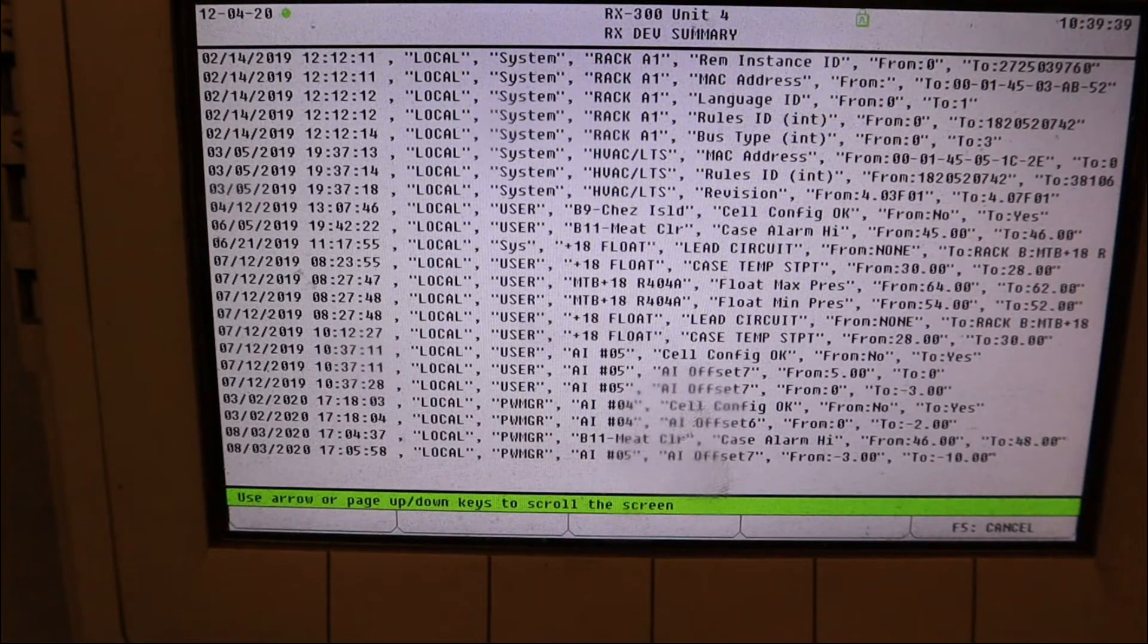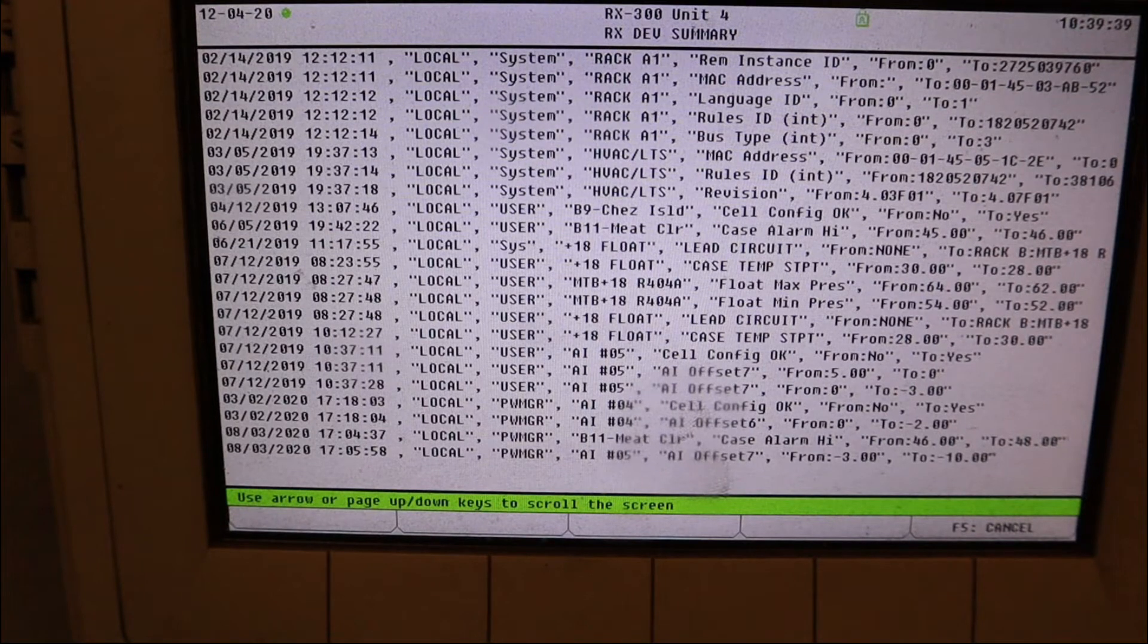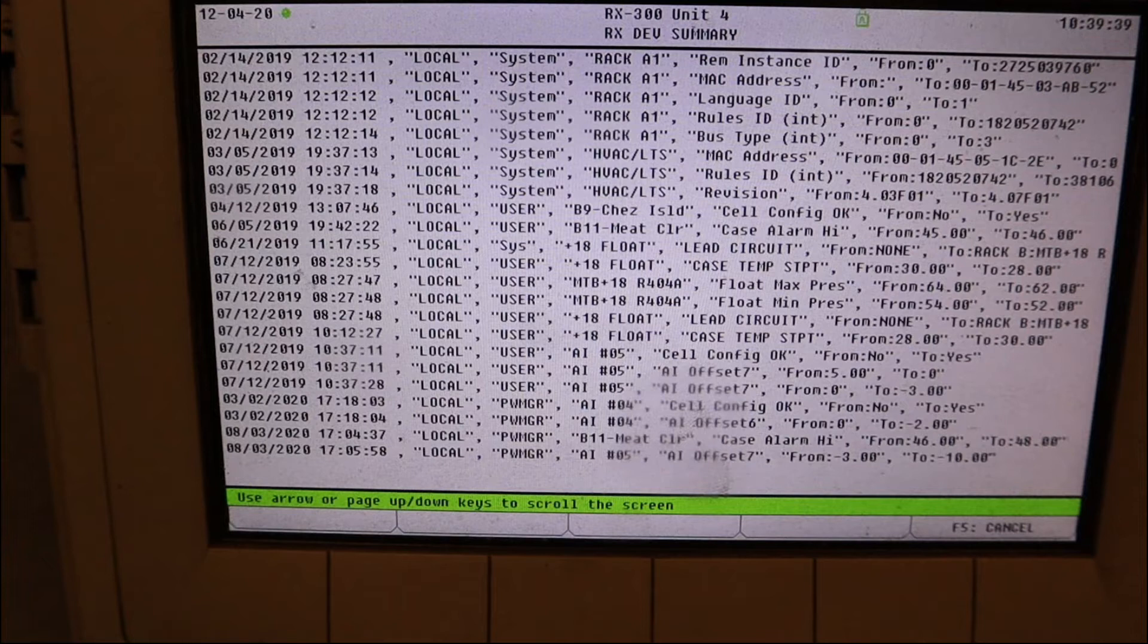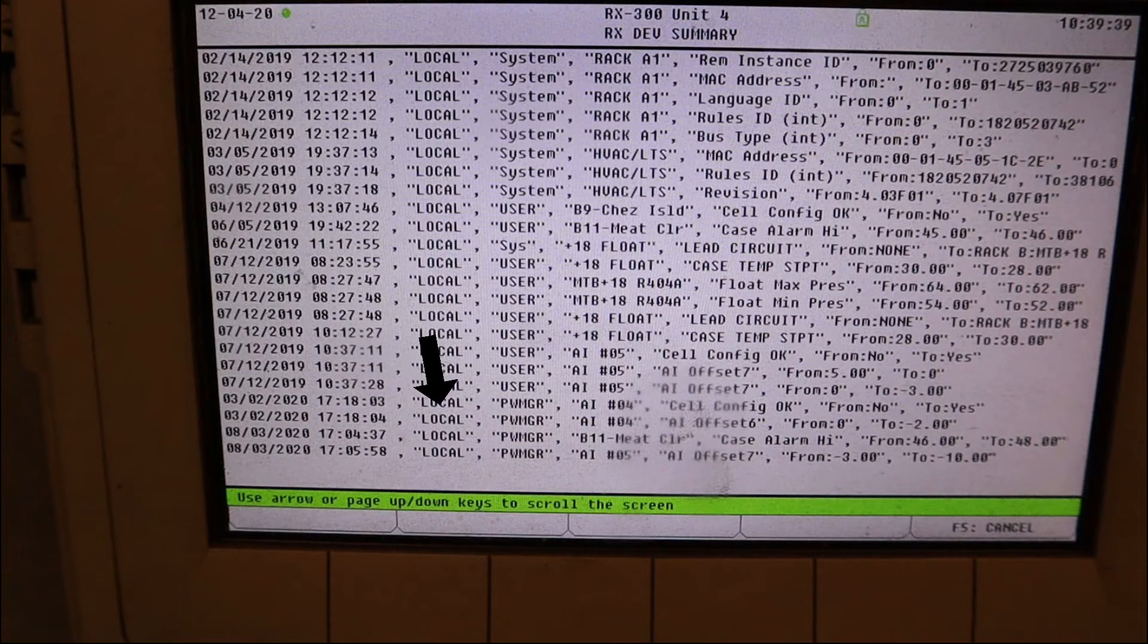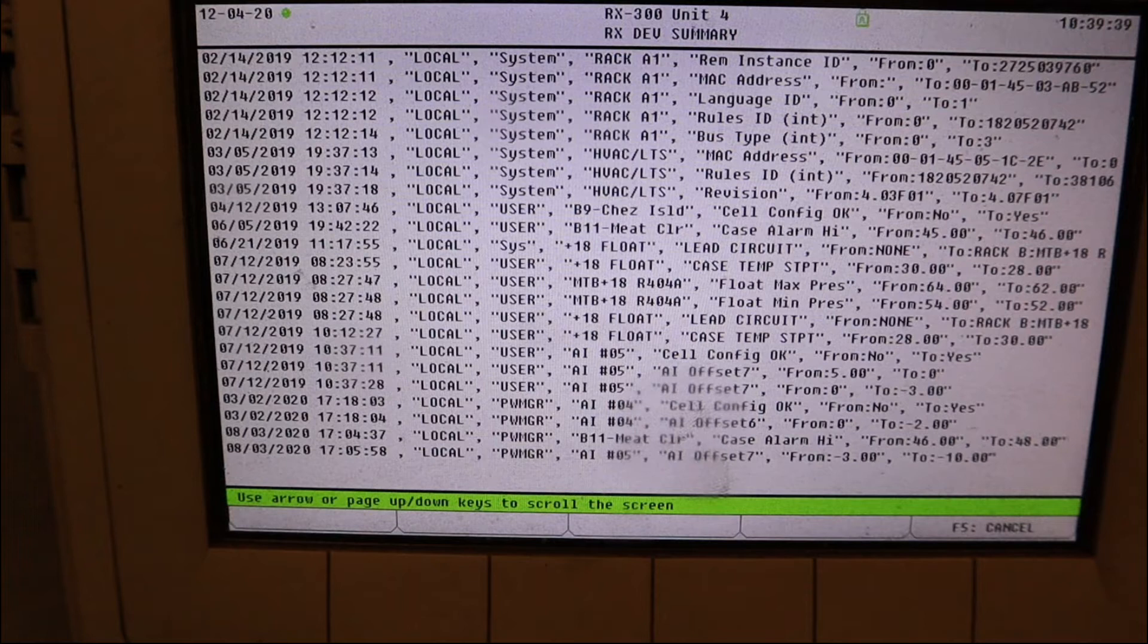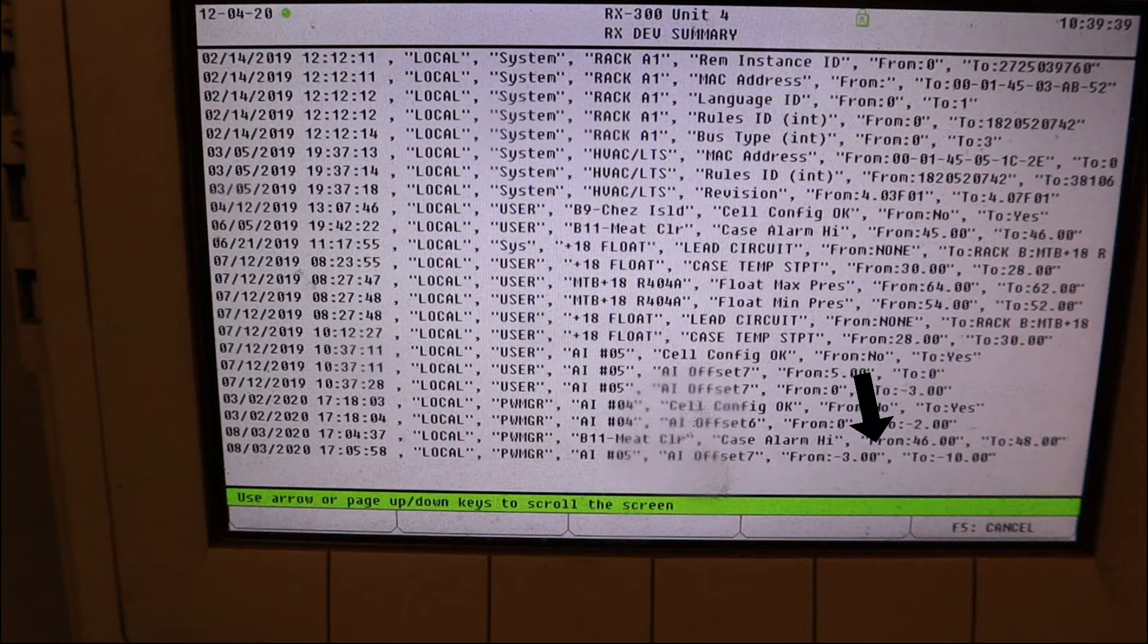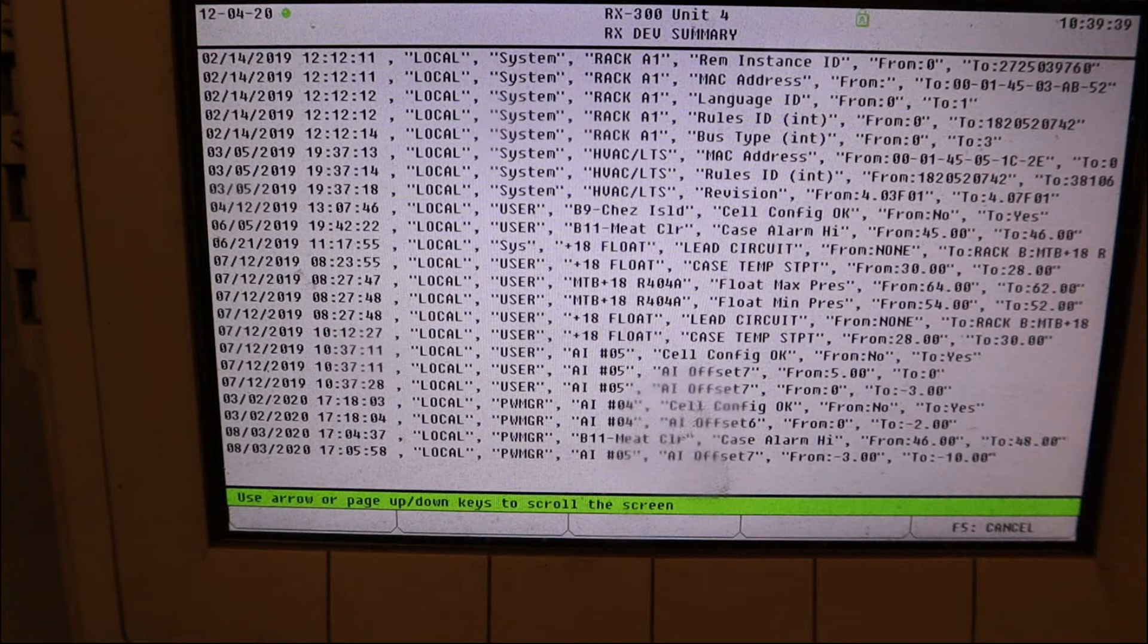I'm going to pause it right here so you can see the screen, all the information in it. You have the date, the time, if it was done remote or on site, what password they used for the change, what system it was, and what they did to that system. You can see here at the very bottom they put an offset from minus three to minus ten. Why? That's when you can give him a call. See, hey, what's going on here?